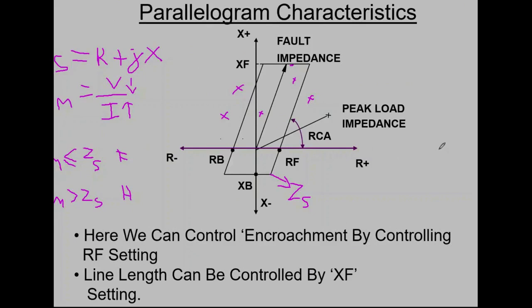Charging of a transformer, the transformer will take sudden current, and that will be for a short duration, not for a very long duration. So maybe 250 or 300 milliseconds. Then after that, it is going to come down. Now, why we are discussing this is, during that short duration, we are actually creating this scenario.